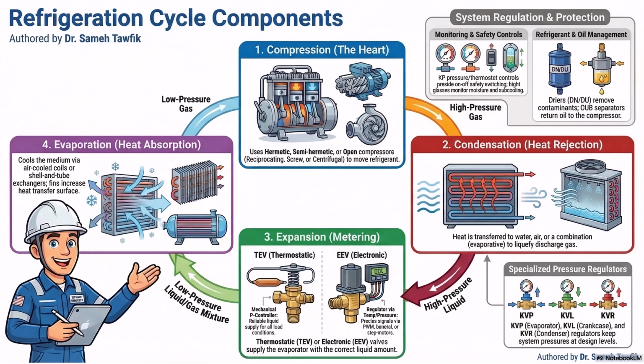Right, because liquids don't compress. Exactly. If a slug of liquid refrigerant hits those spinning impellers or pumping pistons in the compressor, it's like throwing a wrench into a spinning engine. It would be catastrophic. The pistons would slam into an incompressible wall, violently destroying the machine. So it's a bouncer for sure. But how does a purely mechanical valve, I mean, without any electricity or computer chips, know exactly how much liquid to let in to maintain that superheat? That is the genius of the mechanical TEV. It's essentially a blind bouncer that relies entirely on physical pressure.